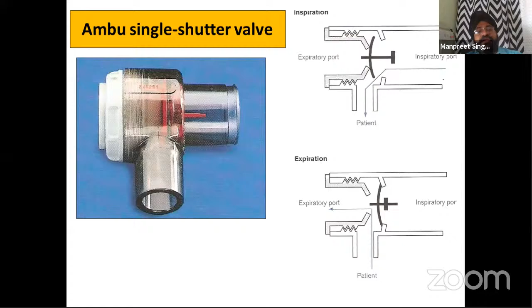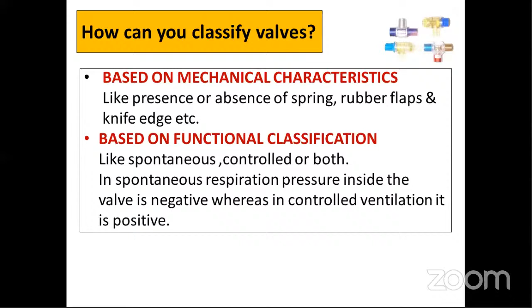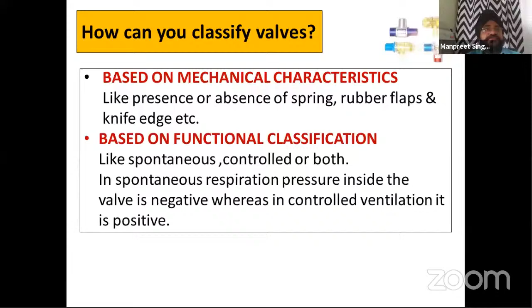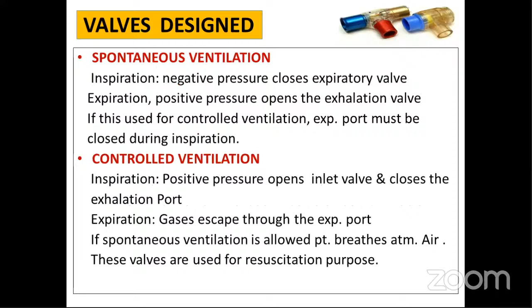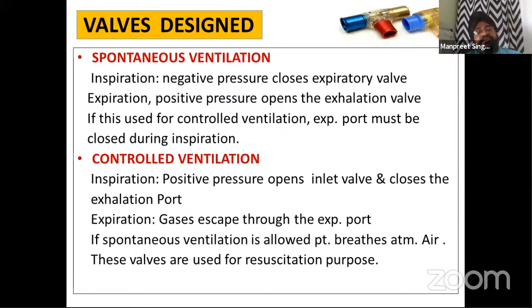Then how do you classify these valves? The question may come. It is based on the mechanical characteristics like presence or absence of spring, rubber flap, or there can be a knife edge, etc. Or this is based on the functional classification, like whether it can be used in spontaneous, or it can be used in controlled, or both. In the spontaneous one, during inspiration, negative pressure closes the expiratory valve, and during expiration, we give the positive pressure, it opens the expiratory valve, and this is how it functions. In controlled ventilation, inspiration is a positive pressure because the patient is in the controlled mode, and it opens the inlet valve and closes the exhalation port.